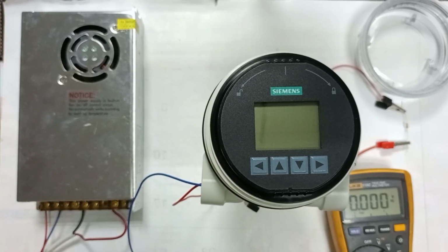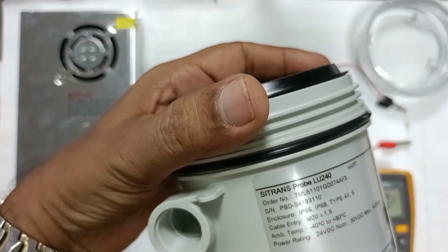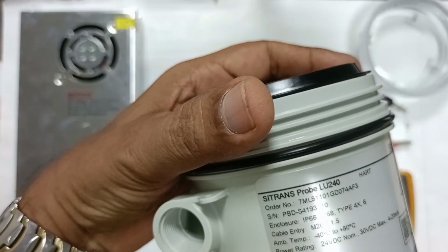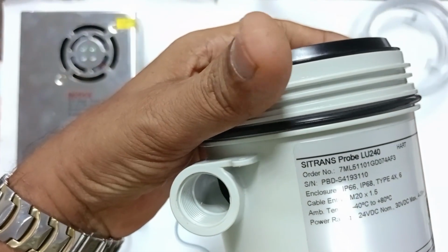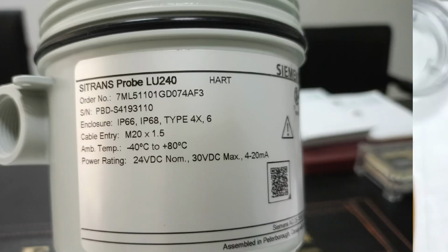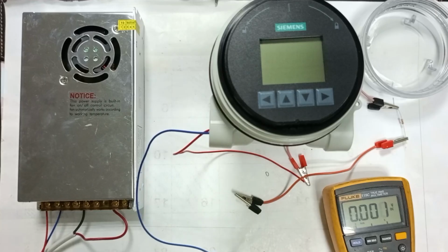Today I will show you how we can complete the installation, commissioning, data setup and field calibration of the Siemens Sitrans radar level transmitter, Sitrans Probe LU240. You see, here is the specification, here is the serial number, enclosure, power rating is 24 volt DC and maximum 30 volt DC, and here is also specified 4 to 20 milliampere. That means we will get output from this transmitter 4 to 20 milliampere, and this output we will use to our PLC panel, and then from there we will get the result from our DCS panel.